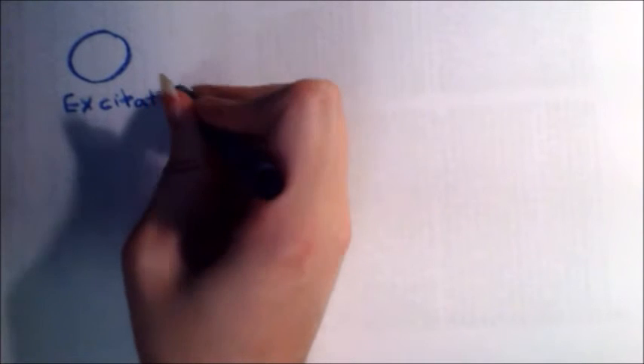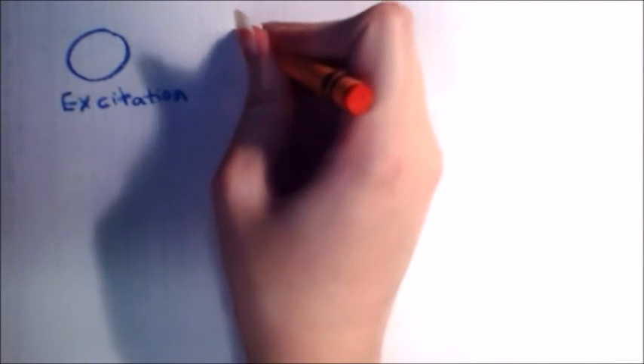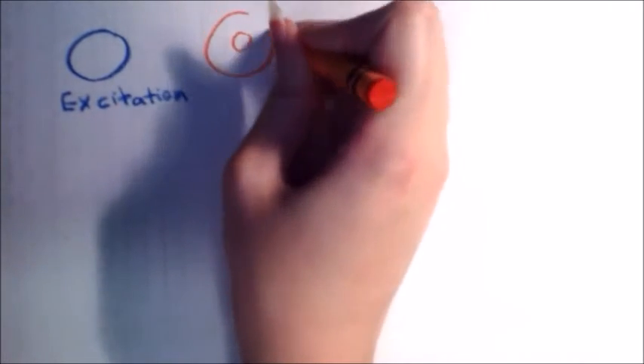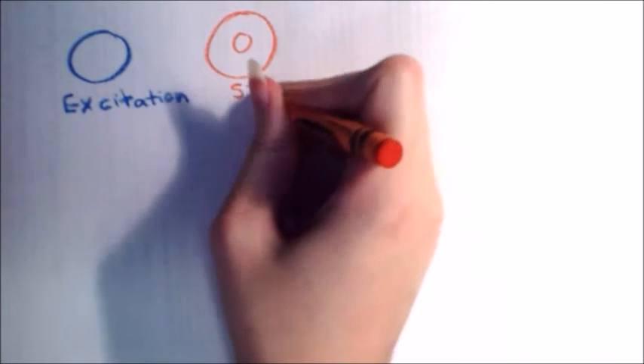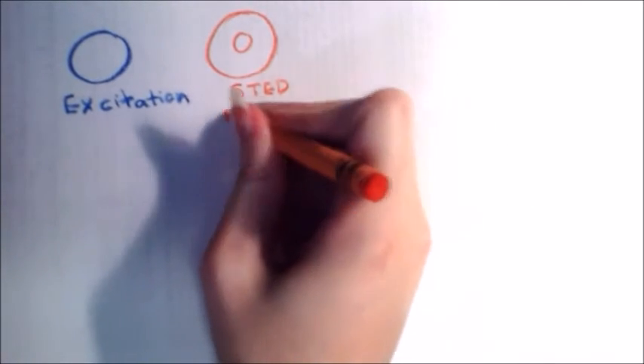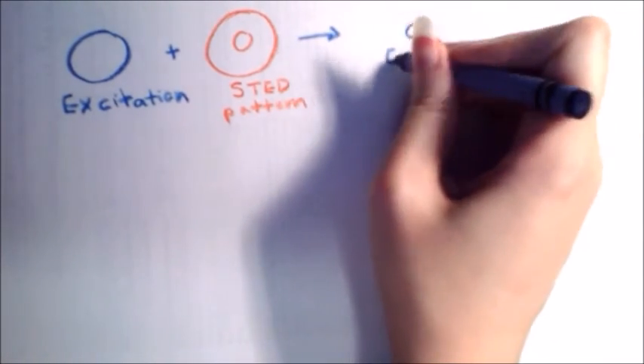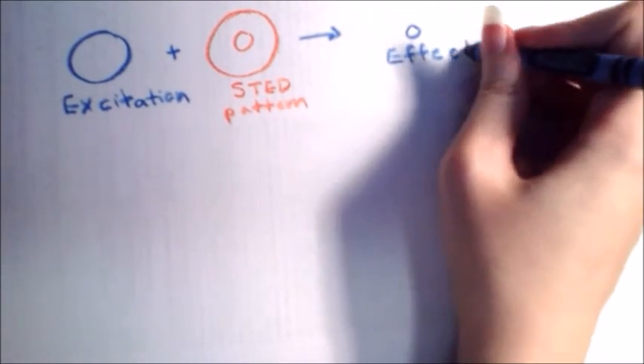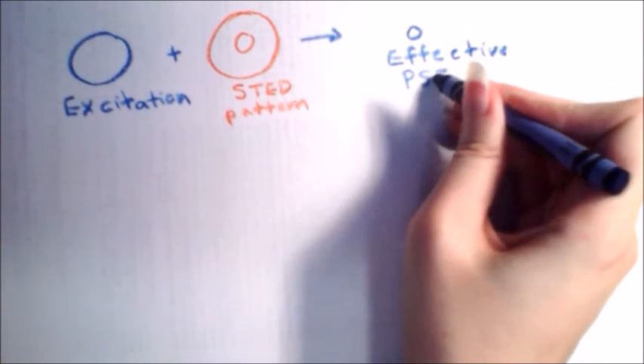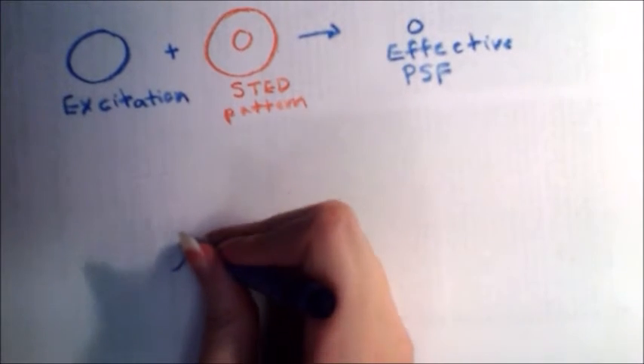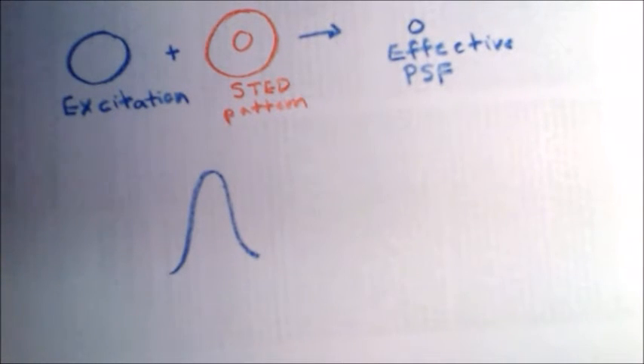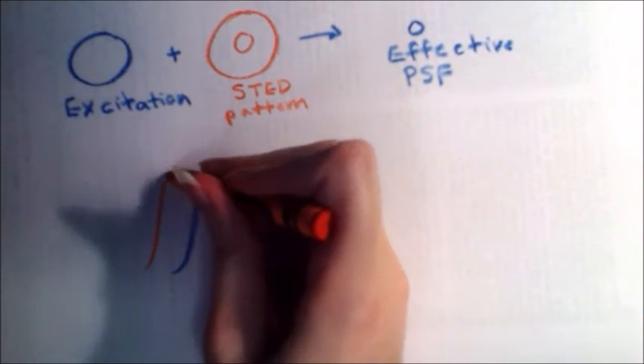Returning to STED microscopy and PSF engineering: in order to reduce the effective diameter of the excitation laser PSF, the periphery can be suppressed using a ring-shaped depletion laser. During STED microscopy, photoswitchable fluorophores are subjected to a scanning excitation laser pulse, followed immediately by a red-shifted ring-shaped depletion laser pulse, which is referred to as the STED beam. As a result, those fluorophores at the center of the excitation beam will freely fluoresce, while those at the PSF periphery will undergo stimulated emission, producing wavelengths that will be blocked from detection. Since only those fluorophores near the center of the PSF are detected, this combination of laser pulses creates a smaller effective PSF, resulting in an improved image resolution.